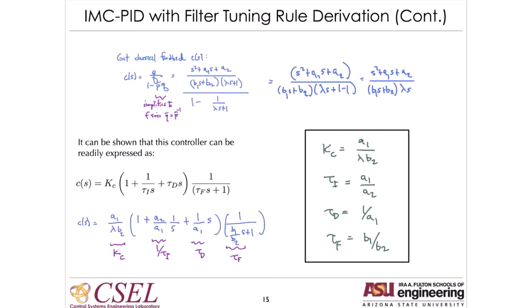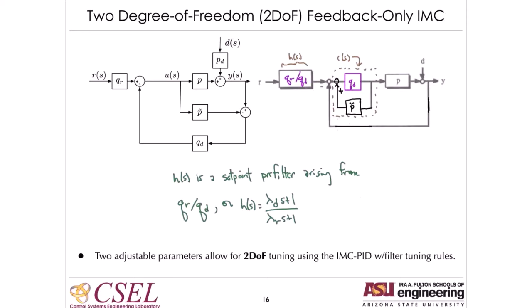We want to also tune separately for set point tracking and disturbance rejection, and we can do that by specifying different lambdas, and then we can rearrange that into a classical feedback system with a pre-filter. So we have a lambda for set point tracking, a lambda for disturbance rejection, and hence the 2 degrees of freedom.